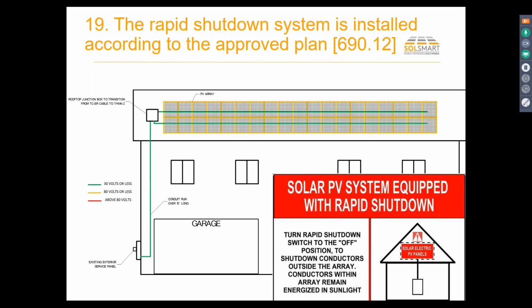So let's say this is a microinverter system. We turn off a circuit breaker in the main panel down here. That turns off the AC line. That AC line goes all the way down the array. And now the modules just have their open circuit voltage, which might be 40 or 50 volts on them. And that's all that's left. That's the only voltage that's left in the system.